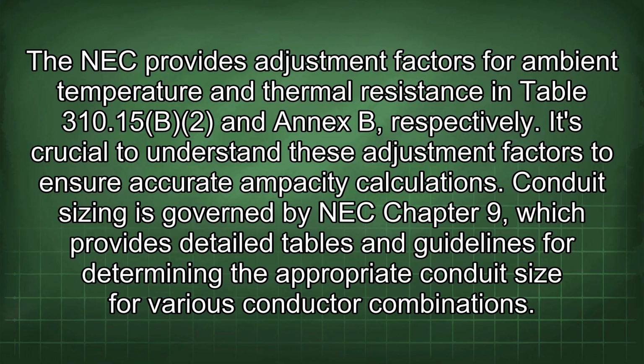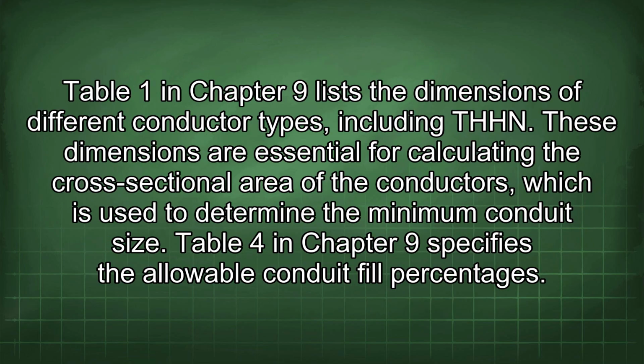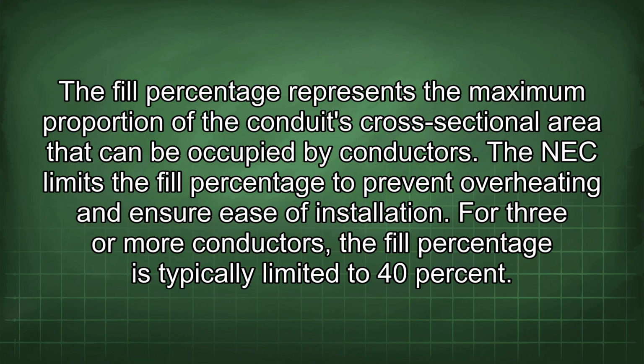Conduit sizing is governed by NEC Chapter 9, which provides detailed tables and guidelines for determining the appropriate conduit size for various conductor combinations. Table 1 in Chapter 9 lists the dimensions of different conductor types, including THHN. These dimensions are essential for calculating the cross-sectional area of the conductors, which is used to determine the minimum conduit size. Table 4 in Chapter 9 specifies the allowable conduit fill percentages. The fill percentage represents the maximum proportion of the conduit's cross-sectional area that can be occupied by conductors. The NEC limits the fill percentage to prevent overheating and ensure ease of installation.